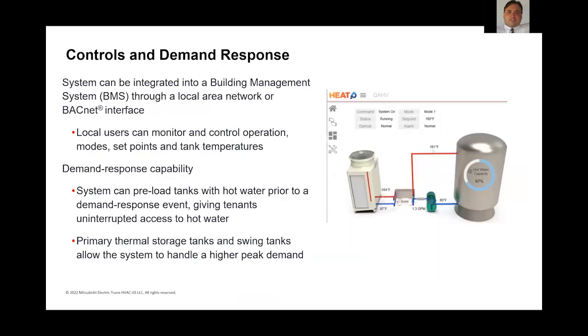So there are higher level controls typically that obviously have to be involved to accomplish this. So you'll find with these systems, they're going to have supervisory panels in many cases. That's the case with Mitsubishi, that have BACnet capability to tie into building management systems to be part of that integrated demand response strategy.